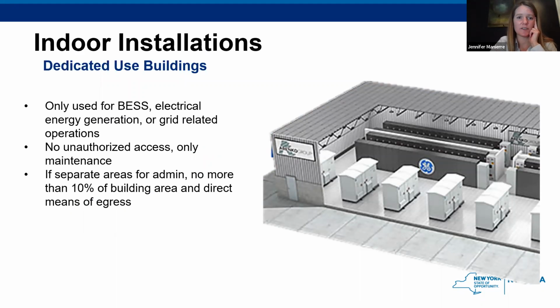Like I mentioned, dedicated use buildings are only used for energy storage. There should be no one going in or out that's not authorized personnel trying to do maintenance. There's one little exception where you can have up to 10% of the building area be an admin office, but it needs to have its own direct means of egress. So no one needs to be walking through the battery storage areas in order to access that admin area. So up to 10% could technically be office and still be a dedicated use building.